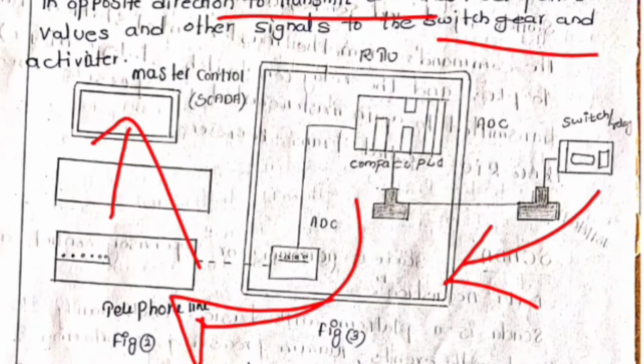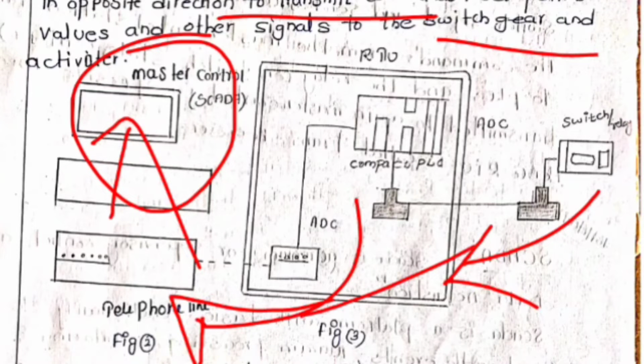What are the functions of the RTU? The main function of the RTU is to receive and transmit. Acquisition of information such as measured values, signals and meter readings; all of this will be stored in the master computer. Transmit commands, instructions, set points and control variables to devices like a circuit breaker. If any circuit breaker is there, the program will be sent to it to transmit the commands. Recognition of changes in input signal state, time allocation, and sequential recording of events at master control stations. These are the various functions of RTUs. Processing of information is transmitted to telecommunication equipment and the remote communication control system.